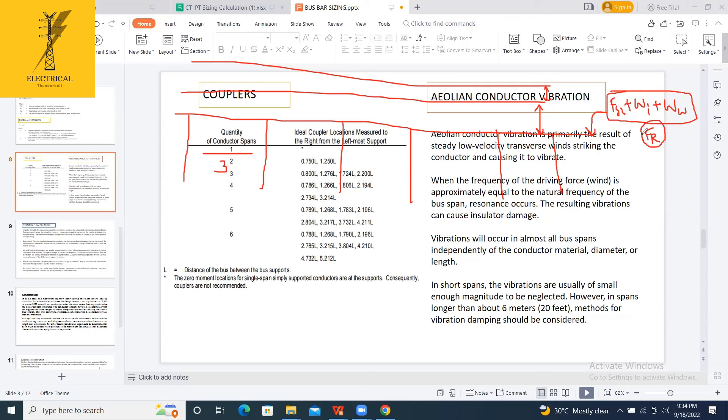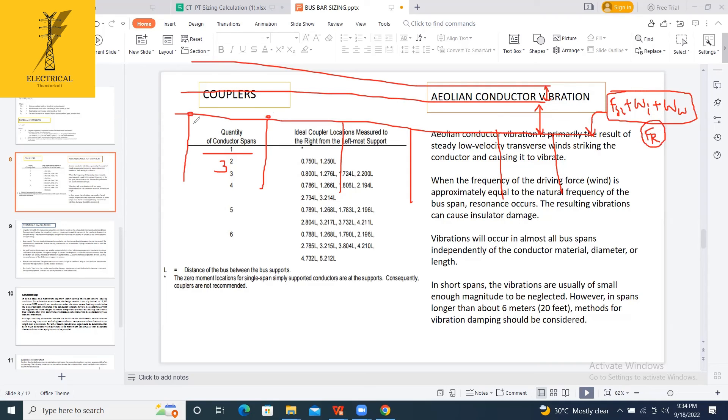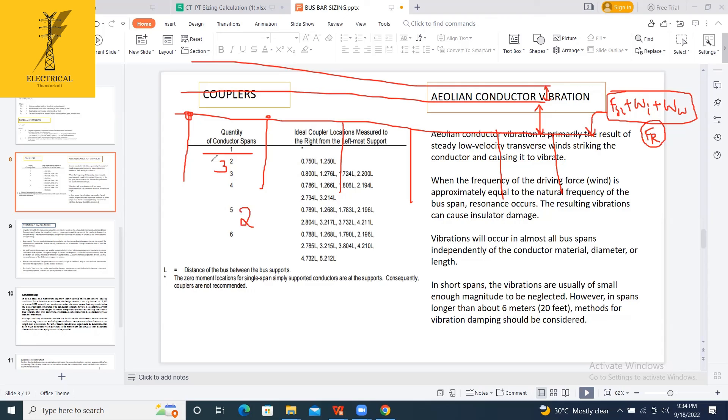Based on this resultant force and some other factors like fiber stress of this conductor and multiplying factors, which depend on whether the conductors are fixed or fixed on both ends, or just supported, or one fixed, one support, based on this, some multiplying factors are there. By considering those multiplying factors, I am concluding what is the minimum span required between the two structures. Suppose if my minimum span required is 2 meters, hence before I selected 3 meters, the selected one is more than the required one, so I can keep this, or else you can reduce this span.